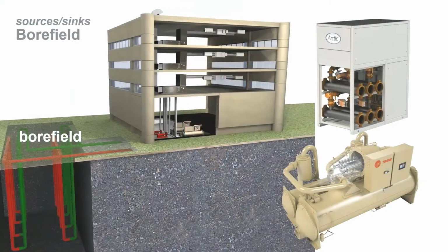Our first example of where BTUs can be found has been around for a long time and is still a great option today: geothermal. A geothermal system consists of a ground source or geothermal loop coupled to the building's HVAC system to reject or add heat to the building as required. The ground loop can come in contact with a large body of water, water pumped from the ground, or a closed loop bore field of pipes buried in the ground. Pictured here is a vertical bore field.